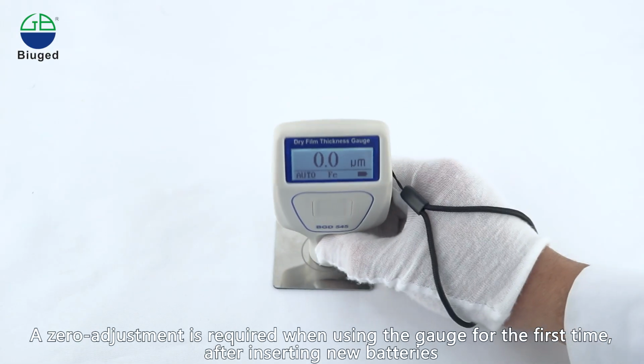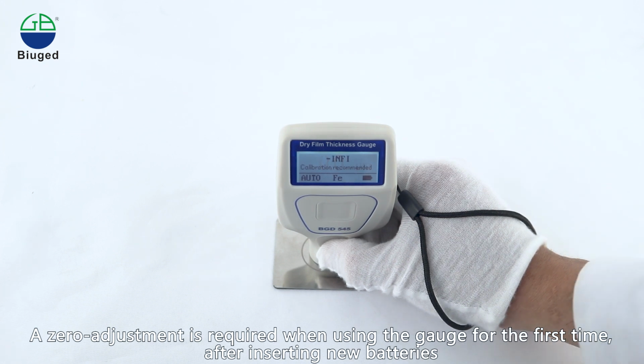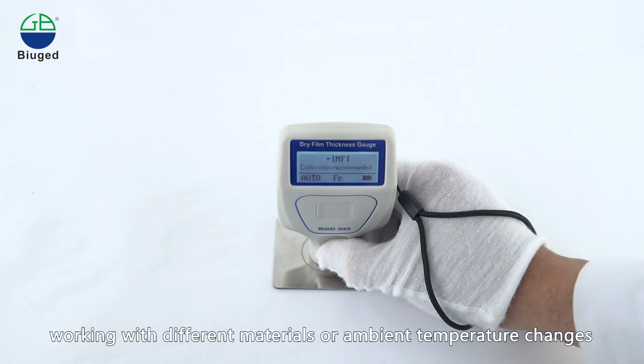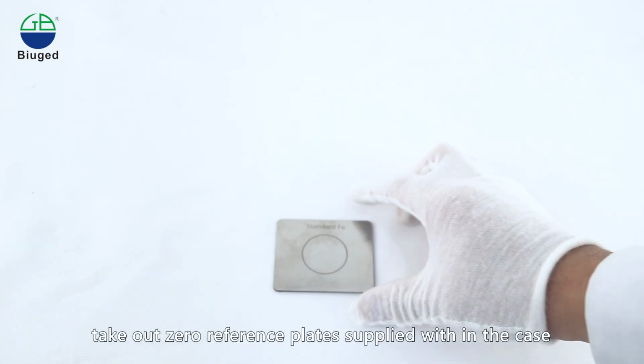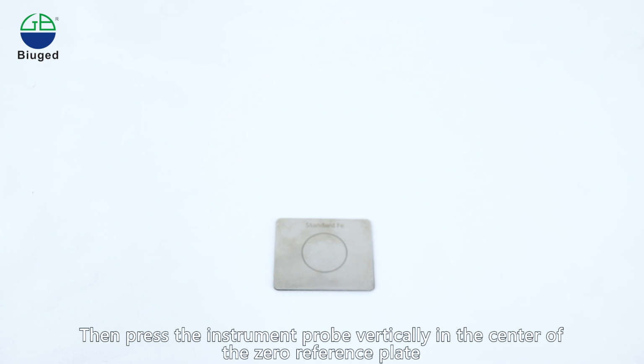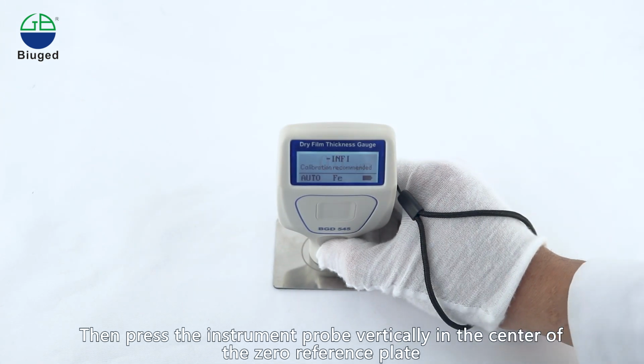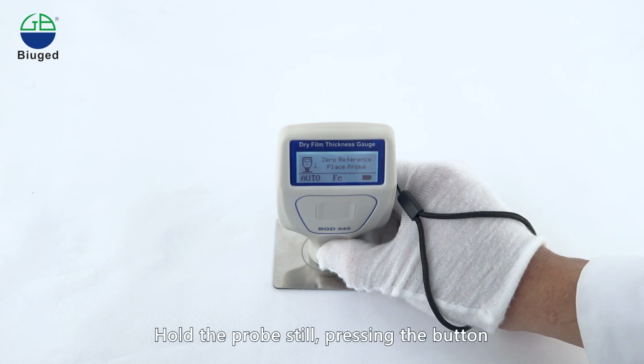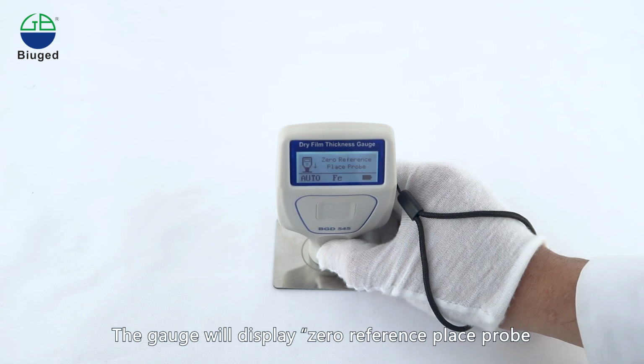A zero adjustment is required when using the gauge for the first time, after inserting new batteries, working with different materials or when ambient temperature changes. Take out the zero reference plate supplied within the case. Then press the instrument probe vertically in the center of the zero reference plate. Hold the probe still, pressing the button. The gauge will display zero reference plate probe.